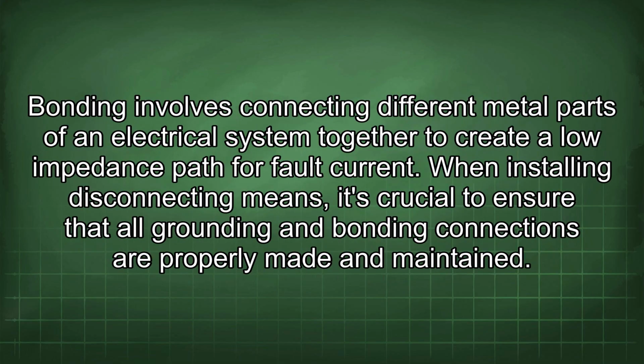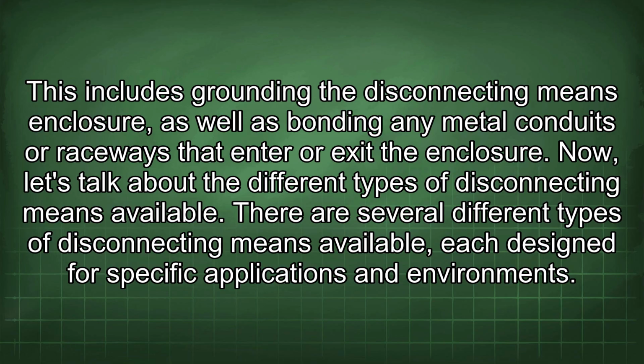Bonding involves connecting different metal parts of an electrical system together to create a low impedance path for fault current. When installing disconnecting means, it's crucial to ensure that all grounding and bonding connections are properly made and maintained. This includes grounding the disconnecting means enclosure, as well as bonding any metal conduits or raceways that enter or exit the enclosure. Now, let's talk about the different types of disconnecting means available.